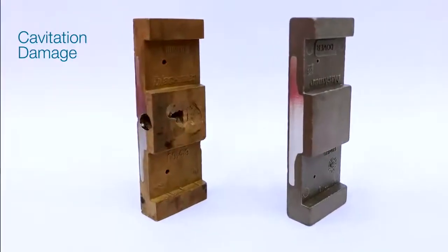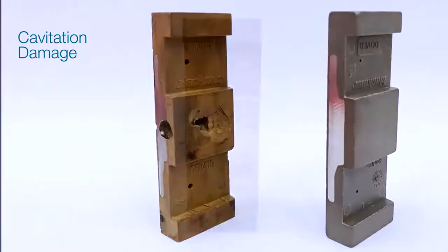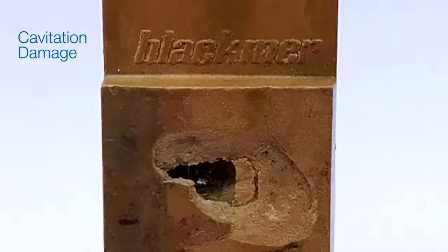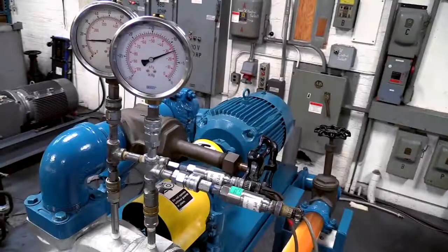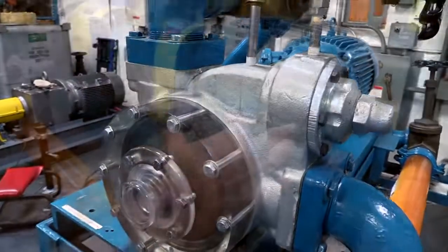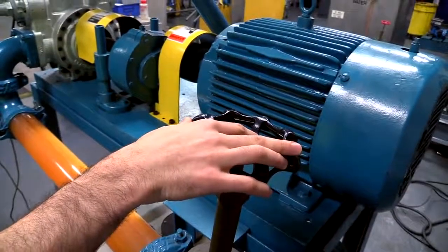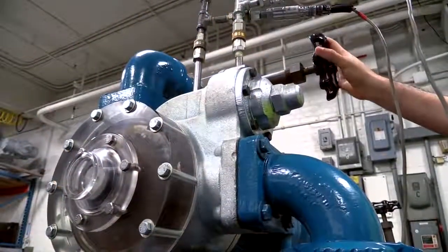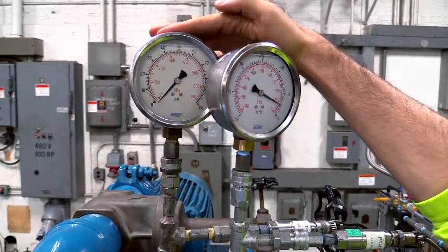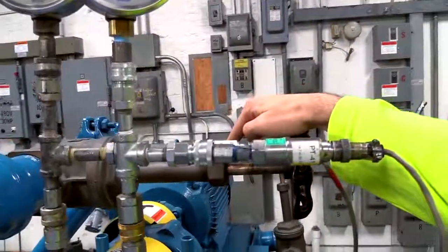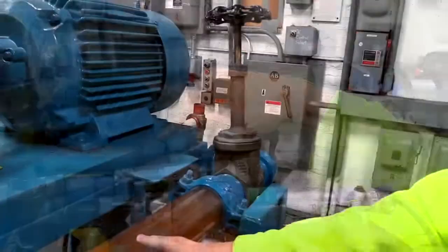And the damage to pumps? Mechanical seal failure, bushing failure, vibration, pitting, or broken vanes. This test lab will allow us to measure conditions and performance and show us how to mitigate cavitation destruction. The test stand has clear inlet pipe runs leading to the pump.